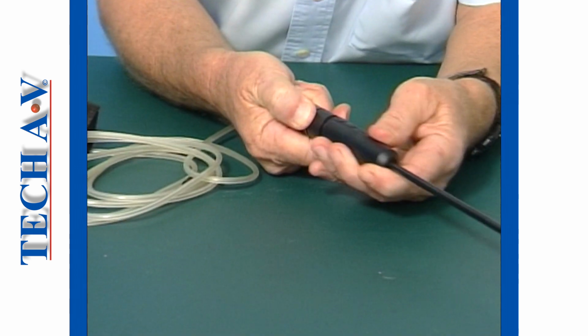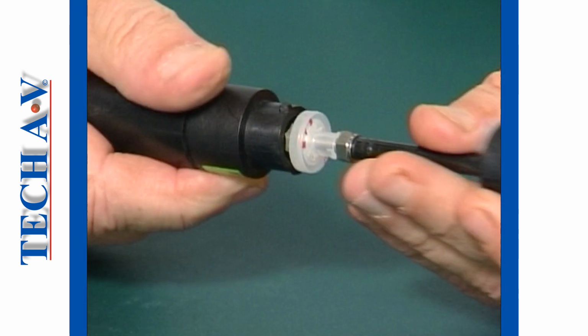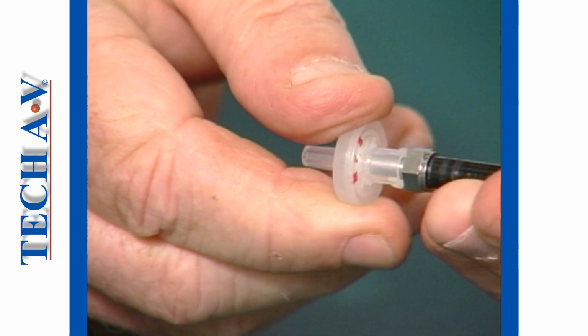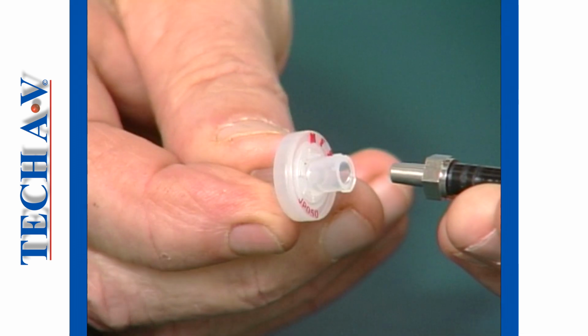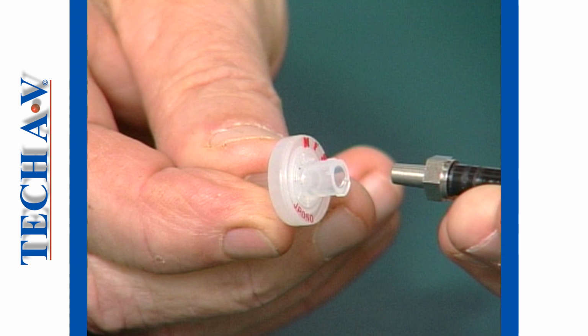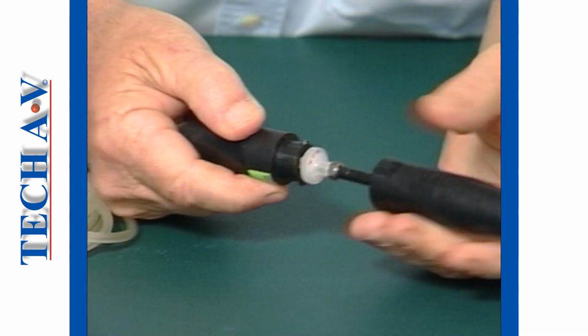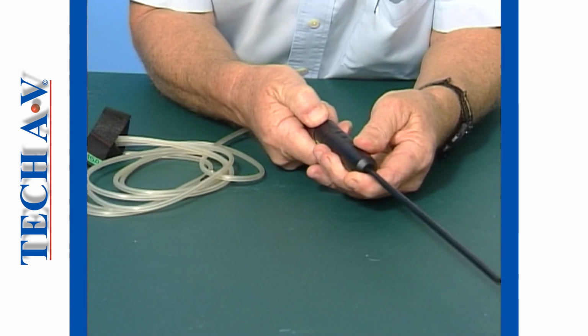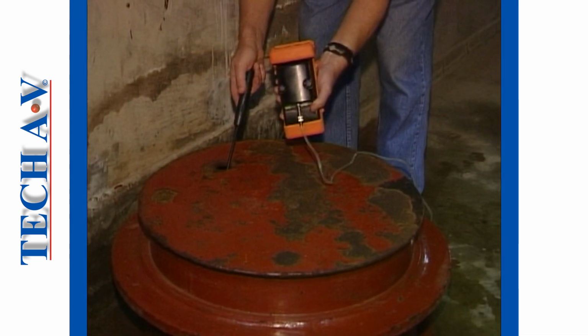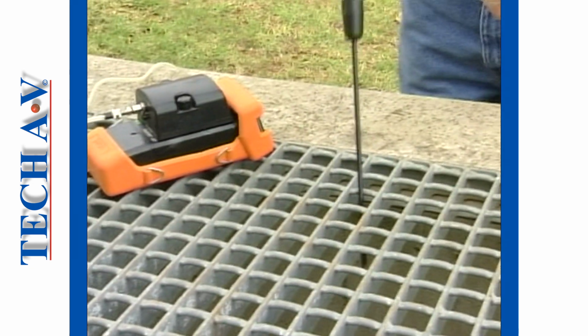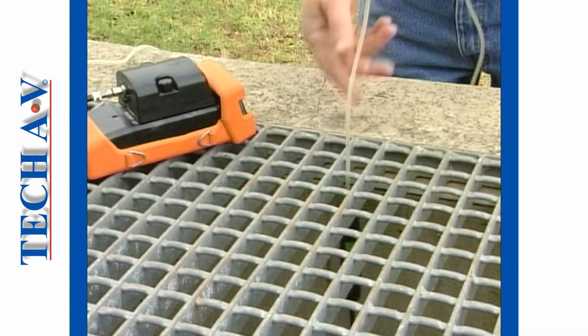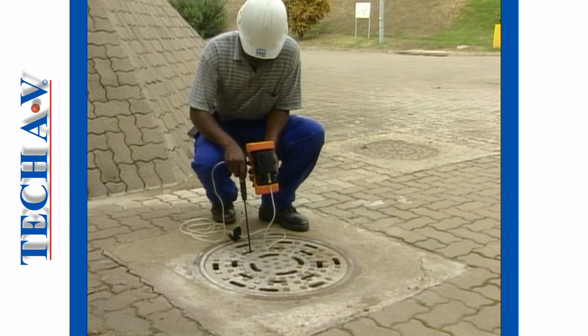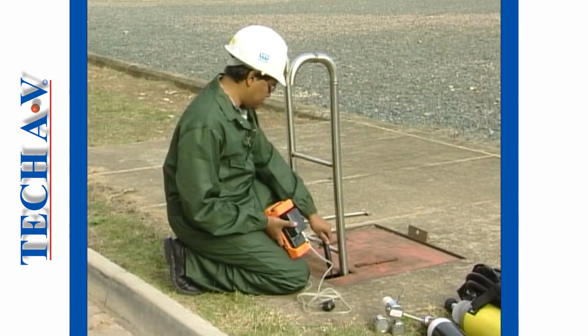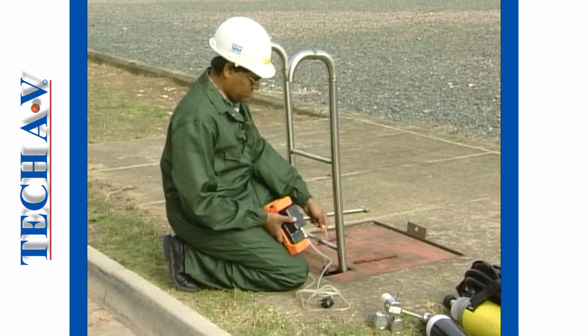Some sampling lines may feature a filter. A filter can prevent the suction of liquid into the instrument, but we should not intentionally allow the probe to enter into liquid, as this will slow down your assessment, as the filter will have to be cleaned and dried, or even renewed before you can continue. Samples of the atmosphere can be taken by introducing the probe into all nooks and crannies that appear likely to contain pockets of gas. At this point, let us break for a practical exercise.